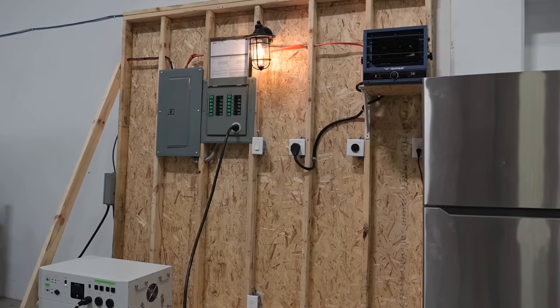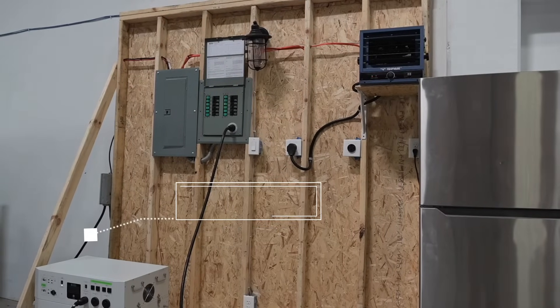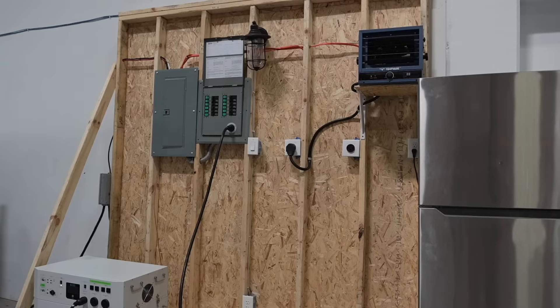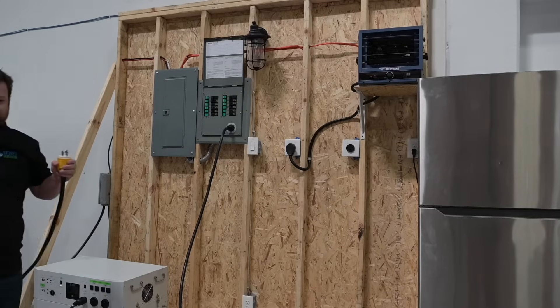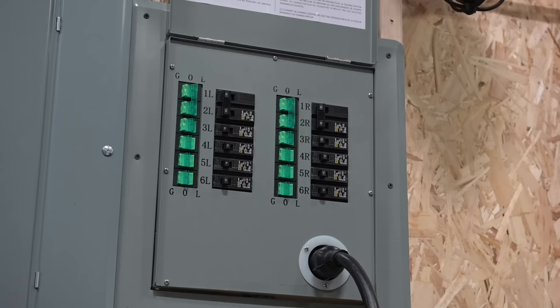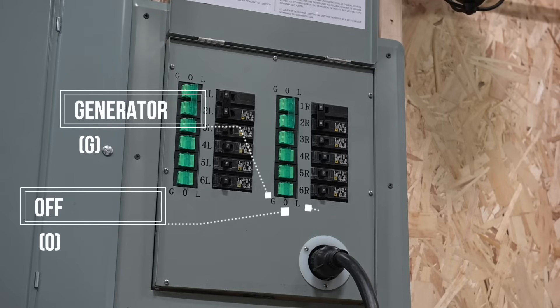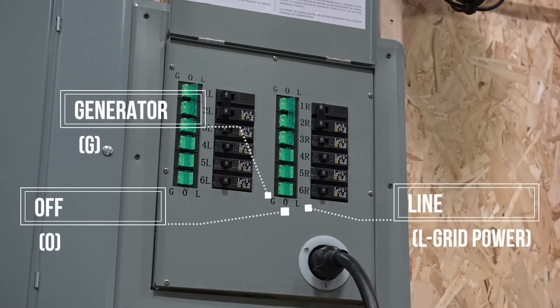In our lab, the demo is hooked up to line power. We'll go ahead and switch off the service disconnect to kill power to the demo, and just to be extra sure, we're going to go ahead and unplug the line power cable altogether. If you take a look at the transfer kit, you'll notice the circuit positions are labeled G for generator, O for off, and L for line, which is also grid power.